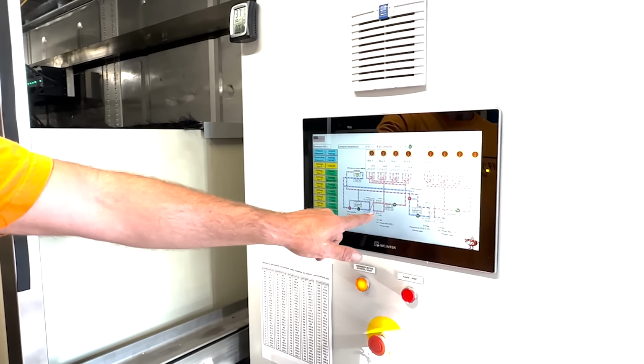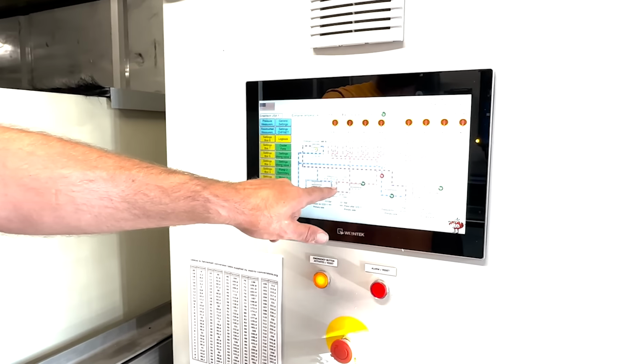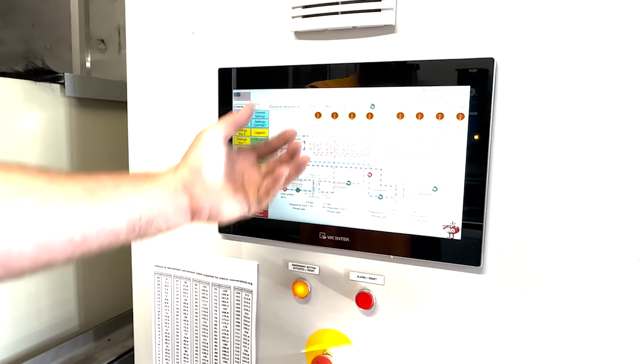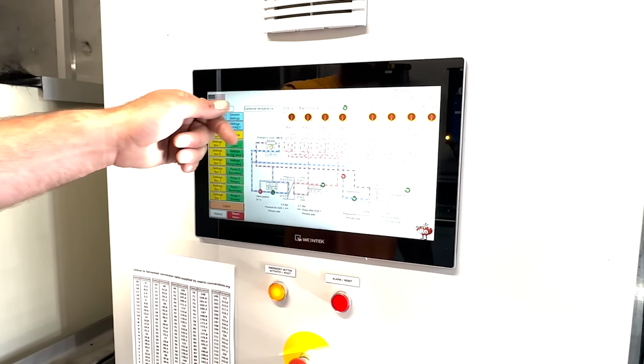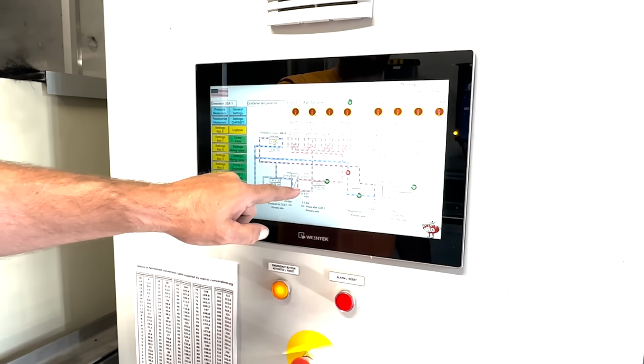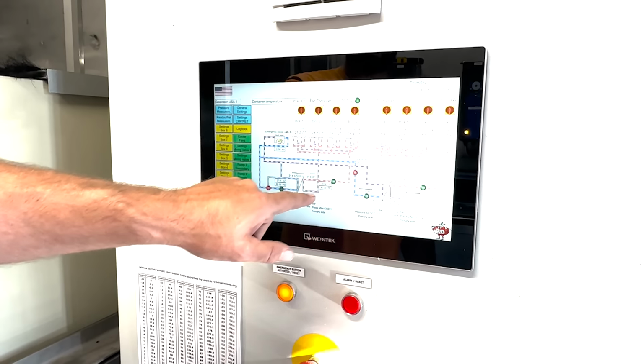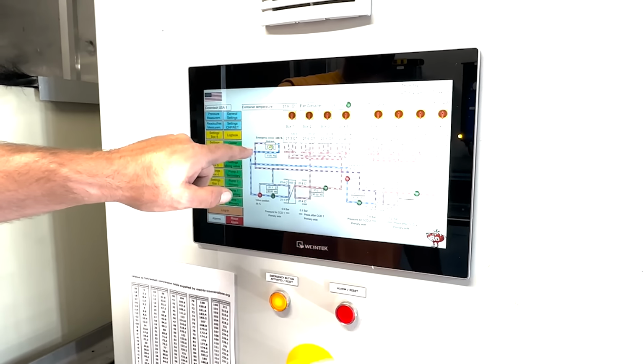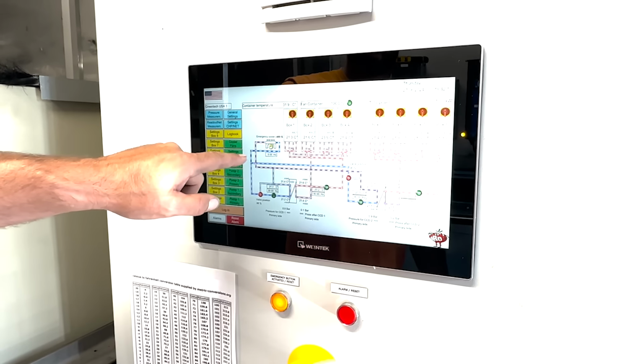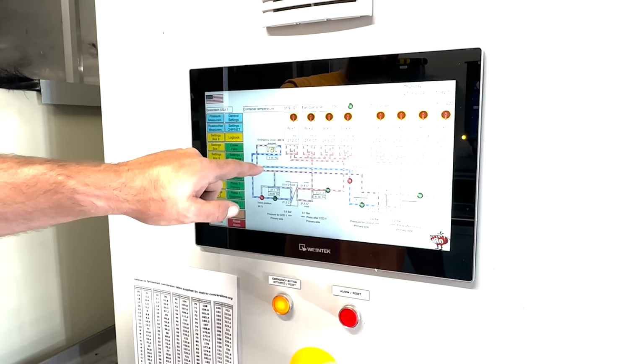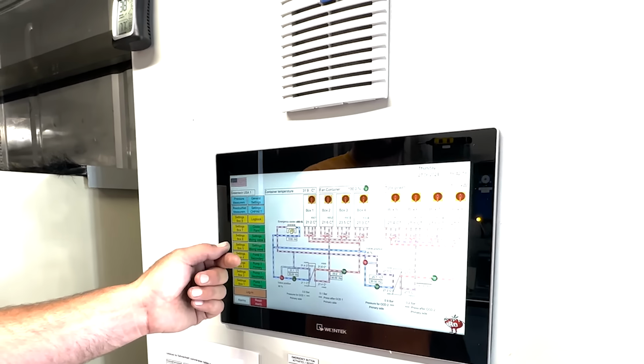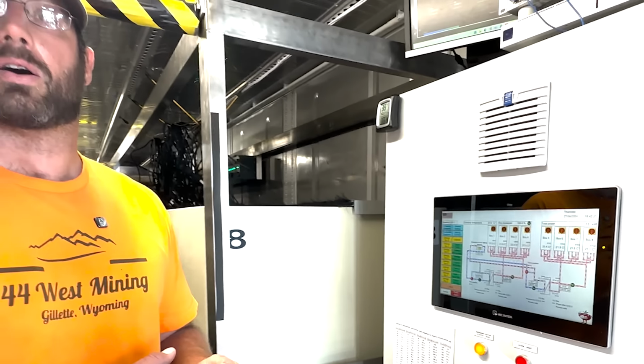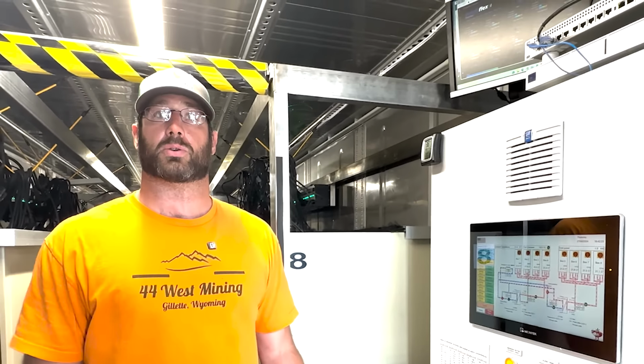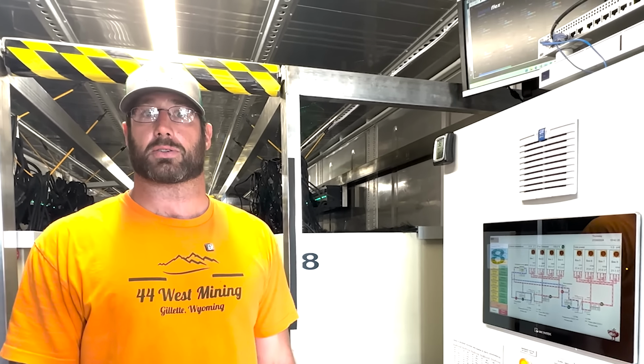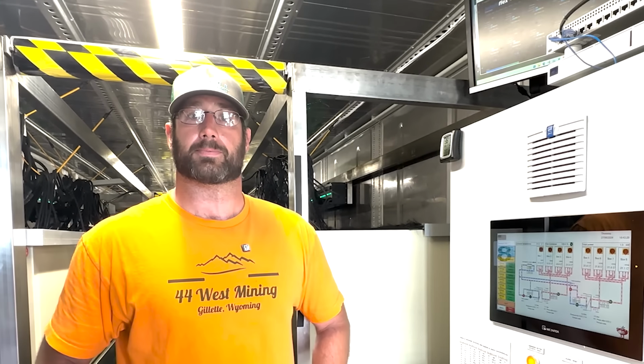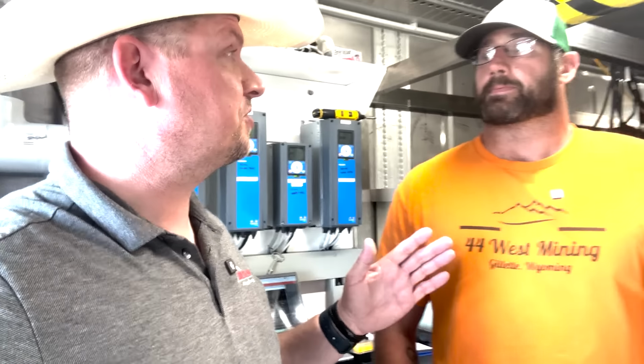So through the heat exchanger, hot oil comes in and goes into the bottom of the tank, where it flows through the tank and then comes out and goes through the heat exchanger again. That's one loop. The second loop has glycol going outside to a big radiator and flowing through the other side of the heat exchanger. It's designed so you could tap into that hot glycol and run a hot water line into a dry cooler in a greenhouse or some sort of radiant heat.